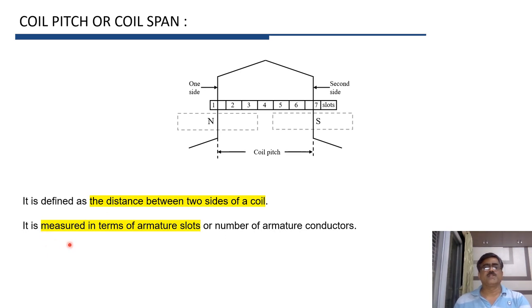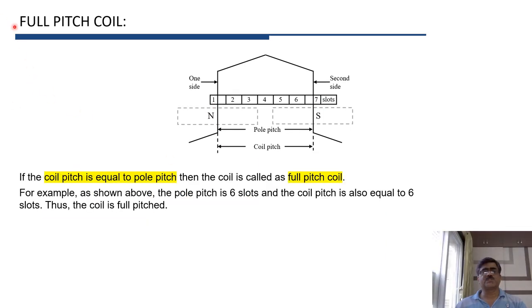Coil pitch is measured in terms of armature slots or number of armature conductors. Coil side 1 is in slot 1 and coil side 2 is in slot 7, so coil pitch equals 7 minus 1, which equals 6. In a full pitch coil, coil pitch equals pole pitch. If pole pitch equals 6 and coil pitch also equals 6, then this coil is called a full pitch coil.